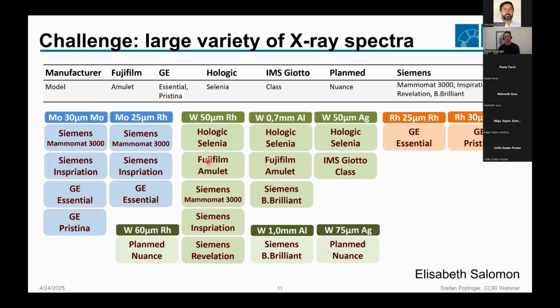The situation is much more complicated if we look at mammography. What you can see here is a list from my colleague Elisabeth Salomon. This is not a comprehensive list, just some mammography devices. And as you can see, there are many different combinations. The first letter always shows the material of the anode, the second letter combination shows the material of the filter, and in between is the thickness of the filter. There are different anode materials and different filter materials. And even if you stay with the same anode material and the same filter material, like here for tungsten and aluminum, you can see that there are different thicknesses of filter. So all of this is changing.